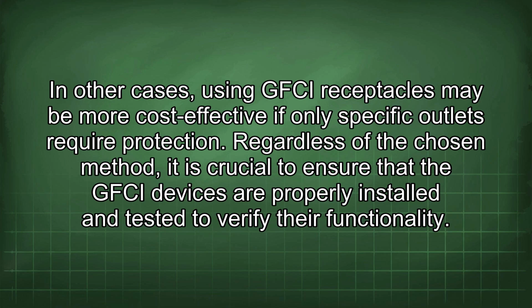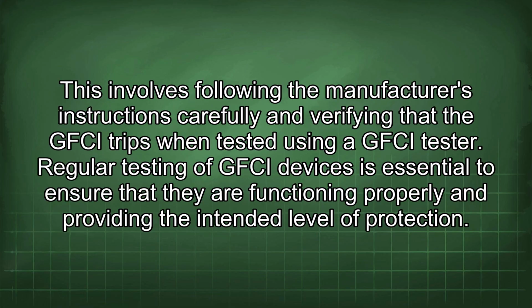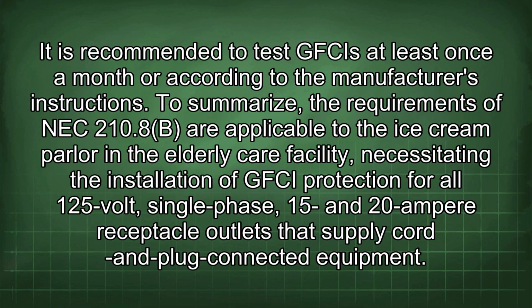Regardless of the chosen method, it is crucial to ensure that the GFCI devices are properly installed and tested to verify their functionality. This involves following the manufacturer's instructions carefully and verifying that the GFCI trips when tested using a GFCI tester. Regular testing of GFCI devices is essential to ensure that they are functioning properly and providing the intended level of protection. It is recommended to test GFCIs at least once a month or according to the manufacturer's instructions.